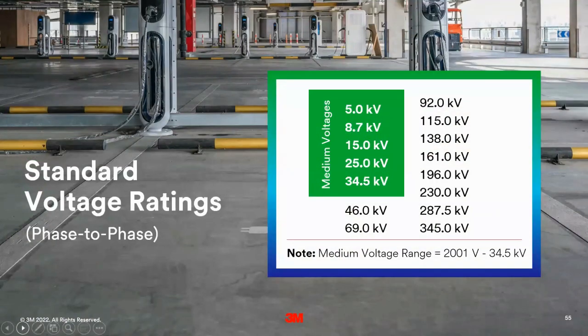And then as far as medium voltage, we consider medium voltage anything from 2001 volts up to 35 kV. So just a rule of thumb there, when selecting cable and cable accessories, it's always good to use the next higher voltage rating. So yeah, 2001 to 34.5. Anything above that we would consider high voltage.